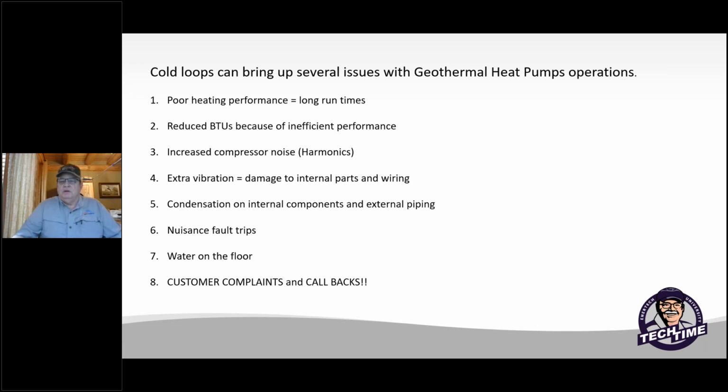One of the bigger things I've been hearing more lately is condensation inside the pan, with water running out of the cabinet onto people's floors. I've got a couple of slides I'll show you in a second with some examples. These kinds of problems also give us nuisance fault trips, customer complaints and callbacks. So why is my unit leaking? A lot of people think it's the desuperheater hot water generator leaking, and typically it's condensation or sweat occurring, which can be eliminated if things are thought out and designed properly.